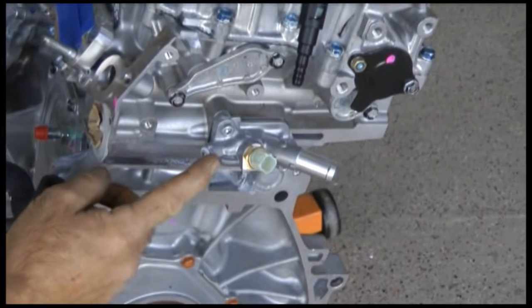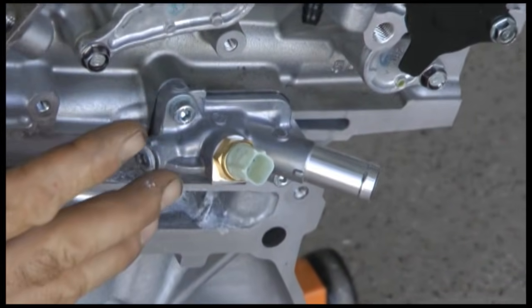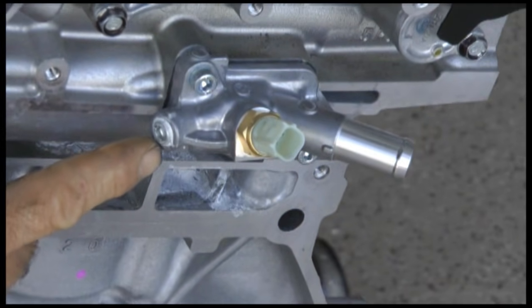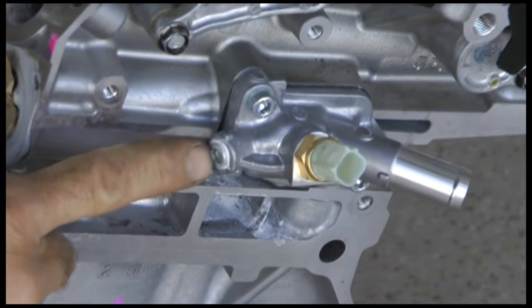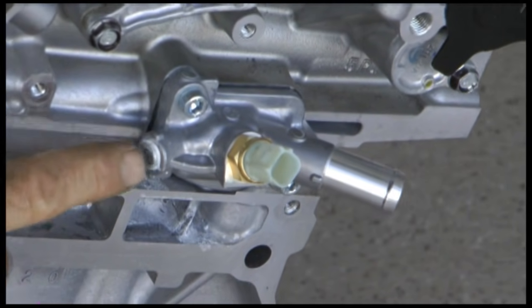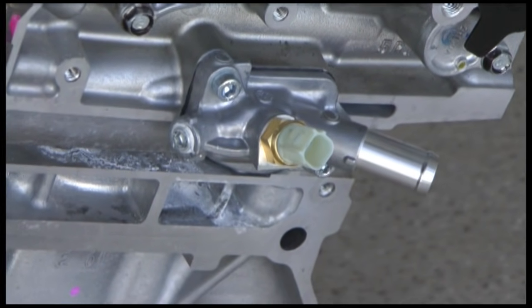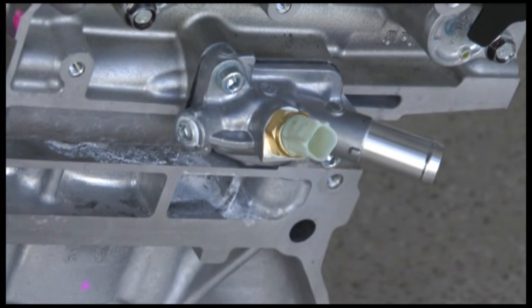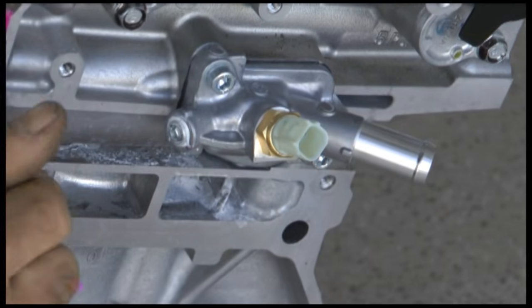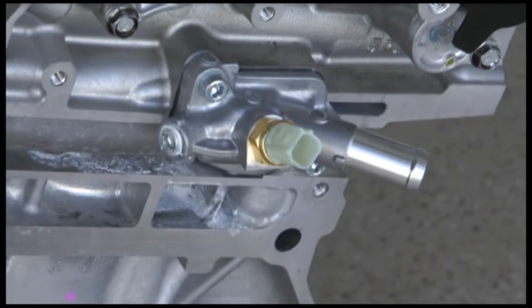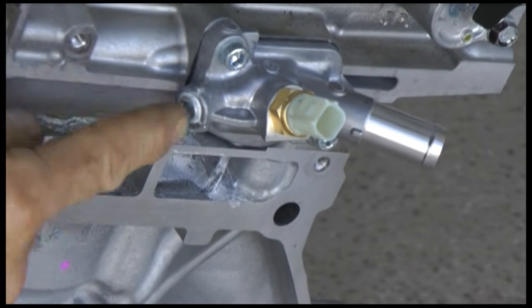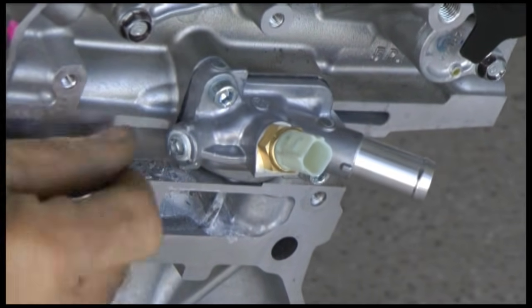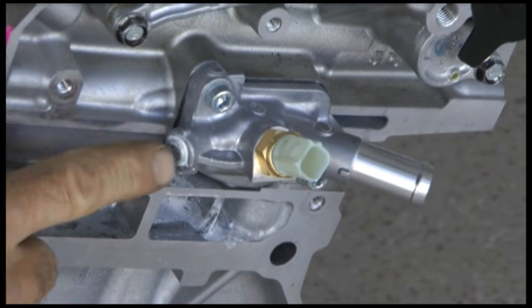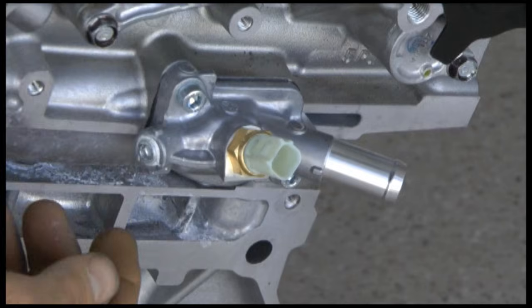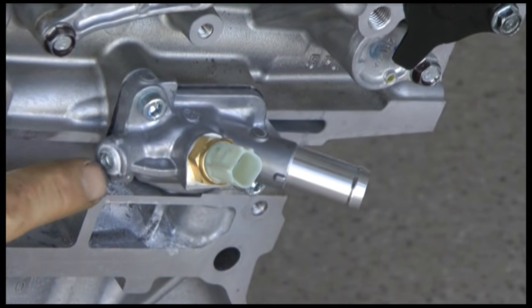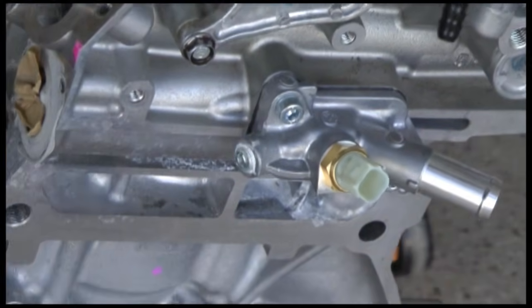This is an area on an engine where the gearbox isn't in place, but we're showing it because it's easier to see on camera. This is an 1/8-inch NPT plug - most sensors that sense temperature for instrumentation use an 1/8-inch NPT thread. Using an Allen wrench next to the gearbox with a ball socket, you can take this plug out and screw in a temperature probe. It's a little tight, but we've done it on a few installations and it is possible. It's a bit inconvenient, but it's the perfect location to pick up the right temperature as it exits the engine.